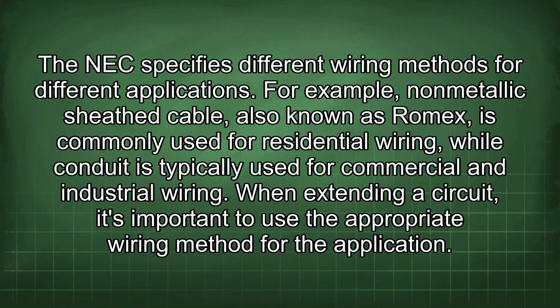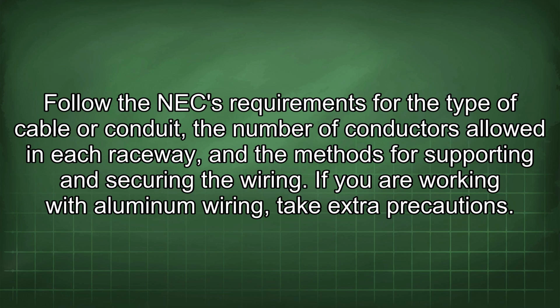When extending a circuit, it's important to use the appropriate wiring method for the application. Follow the NEC requirements for the type of cable or conduit, the number of conductors allowed in each raceway, and the methods for supporting and securing the wiring. If you are working with aluminum wiring, take extra precautions.